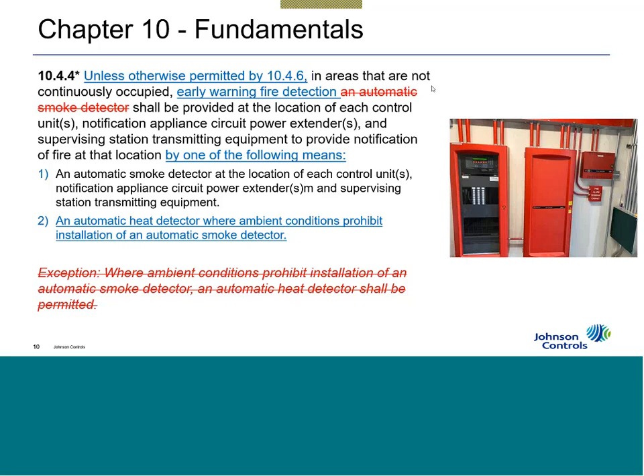is compliments of Norel Fire, a fine AutoCall dealer in the Northeast. If they're all in the same room like this, one smoke detector is fine, as long as it's within 21 feet of every control unit or NAC panel. And if you have 4009s, for example, in closets throughout the building, you need a smoke detector above each one. If you have multiplex transponders out there that have power supplies to activate speakers or horns or strobes, you need a smoke detector above that. So that's the requirement in what's in here.